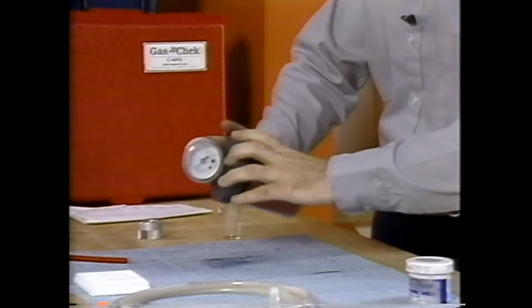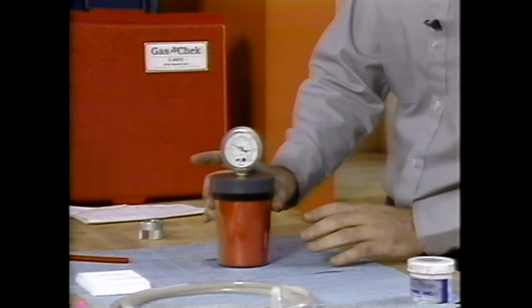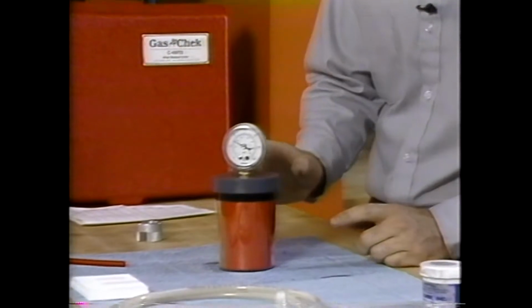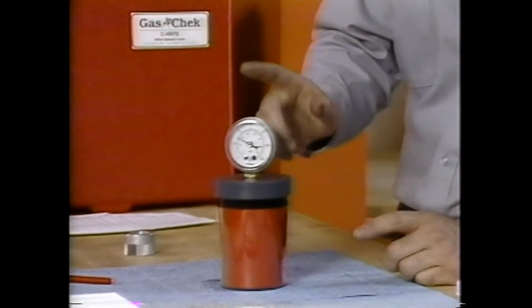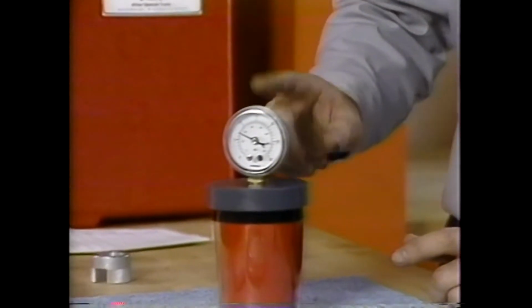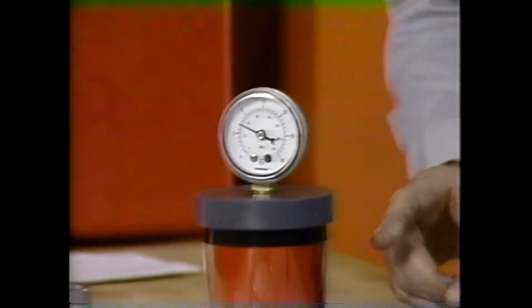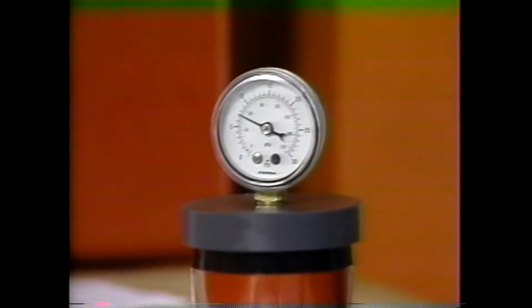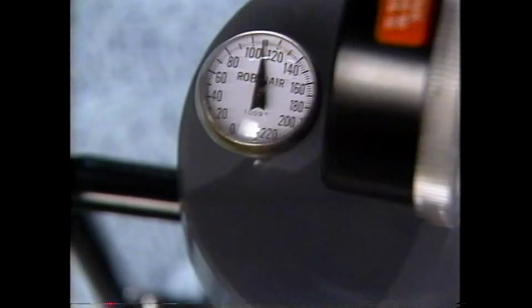Now, once we've done that for a few minutes, put it back upright and take a reading on your pressure gauge. Now, if the needle's fluctuating, tap the gauge to try to get it to settle before you take your reading. It's important that you get a steady reading. And once you've taken your pressure reading, take a look at the thermometer as well, because you have to correlate the temperature along with the pressure when you take your vapor pressure reading in the instruction chart.